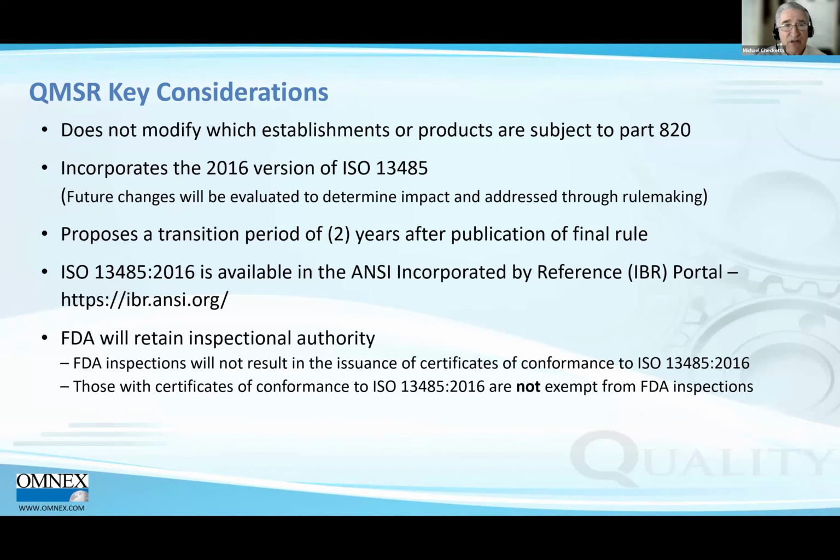QMSR key considerations. These changes do not modify which establishments or products are subject to Part 820. The rules are still the same. Everything that was subject to Part 820 is still subject to 820. It does incorporate the full 2016 version of 13485.